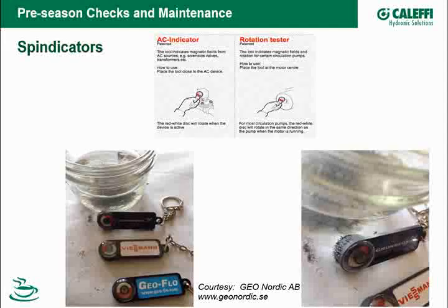Well, that may or may not be true, because basically what this does is it reads a magnetic field in there. So if you put this at the end of the pump, what happens is that little dial on the left-hand side of the spindicator, let me see if I can point to that, will start spinning. But it'll also start spinning if the pump is not spinning. So in other words, if you have a pump that's seized up, it's got bad water quality or something that's seized, or you've got a pump where the shaft is broken off, so the motor's spinning but the impeller isn't, this thing will be spinning, and it can fool you. So to me, really, it almost just tells you that there's voltage going to the pump.